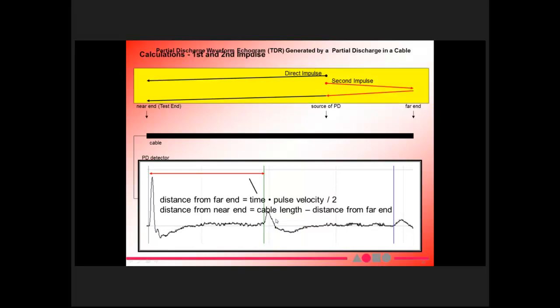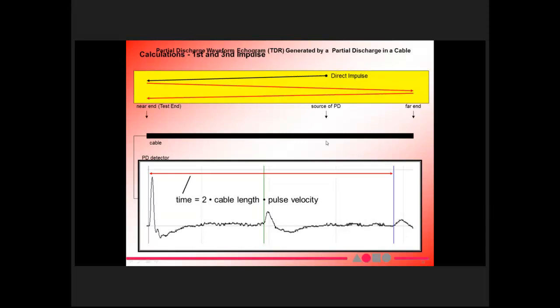Alright, so the bottom line is this distance from here to here is the distance from the cable end. You can take the cable length minus your distance from the far end, and that's where you will walk out from and find your PD site. This distance over here is not that important, but from here to here is really the distance from there to there, which is double the cable length.